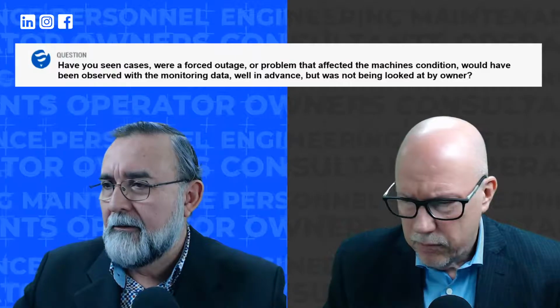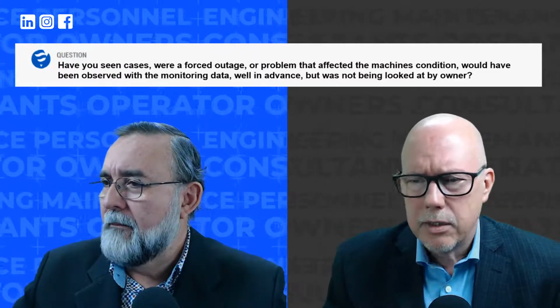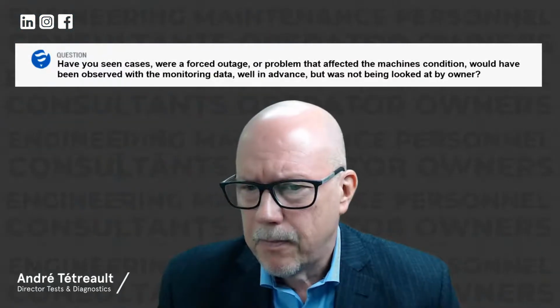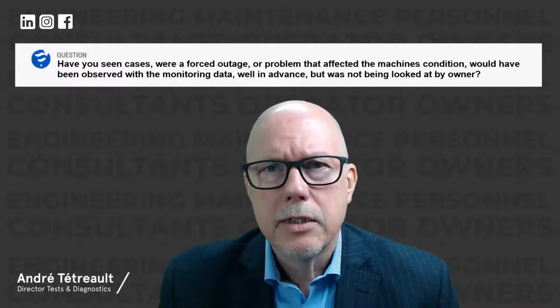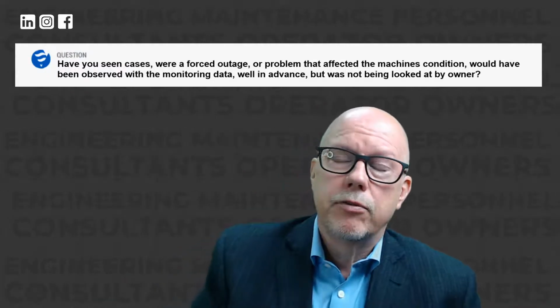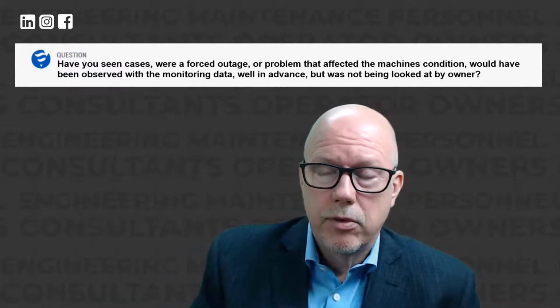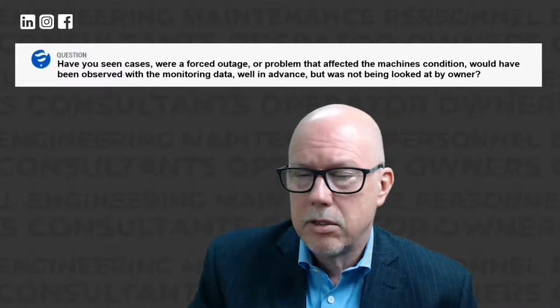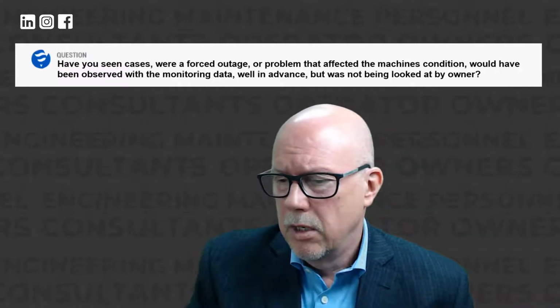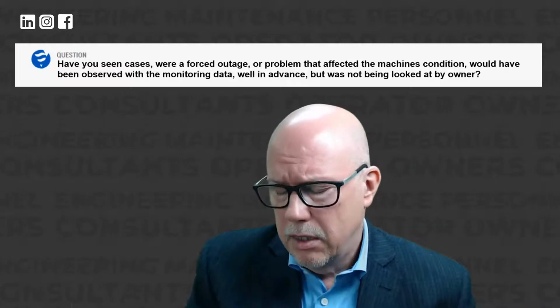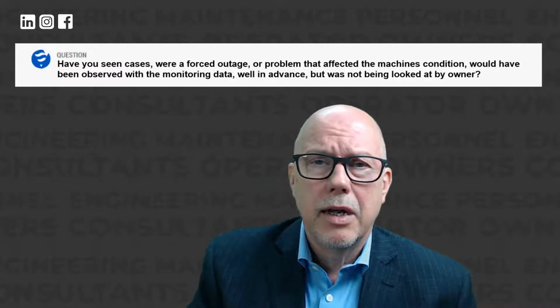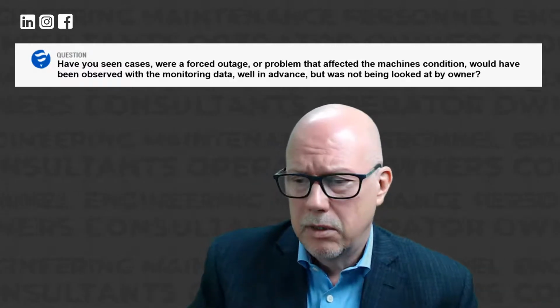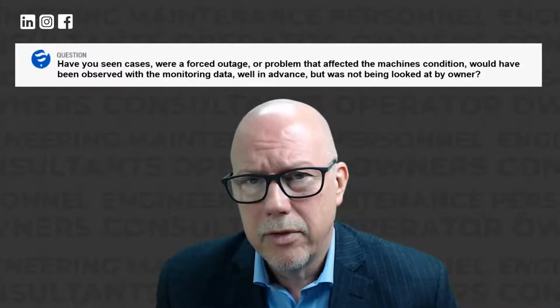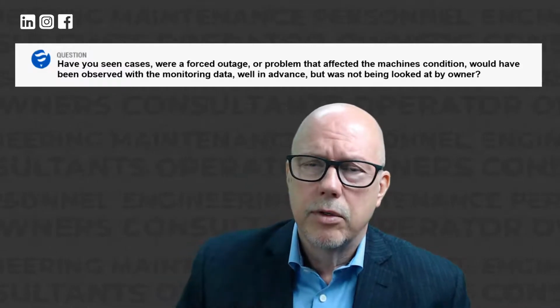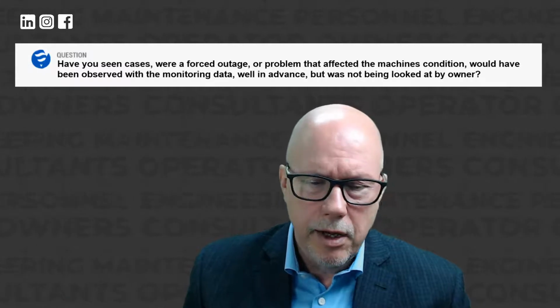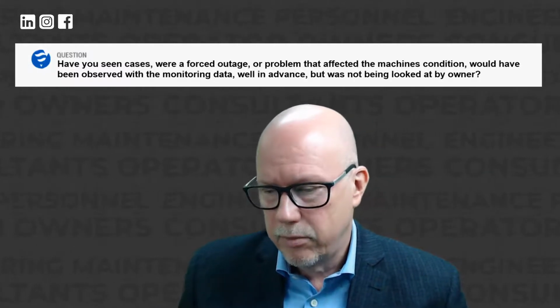Yes, of course, information is power. There are many cases where people focus on different things. For example, the case I mentioned before, magnetic center versus mechanical center, causes all kinds of issues: overheating poles, dovetails that will crack, rims that will crack, stator bar vibration. An offset rotor causes an uneven magnetic field, and that causes all kinds of problems.